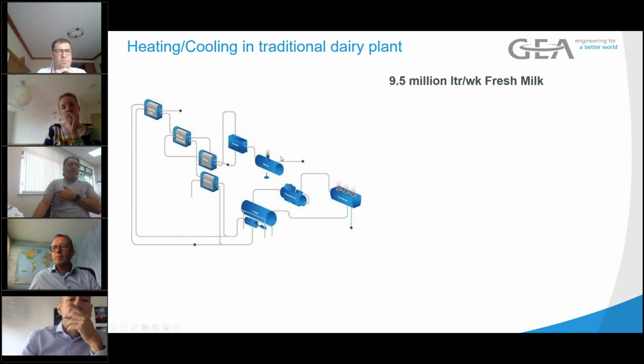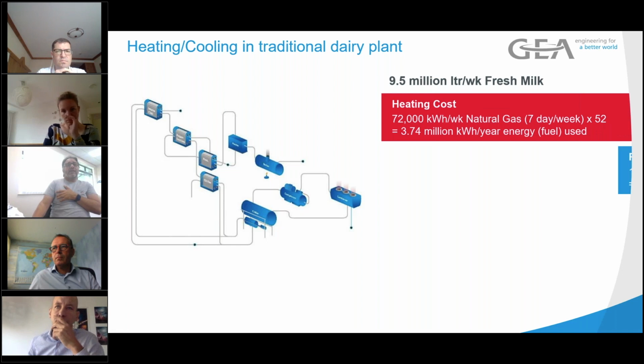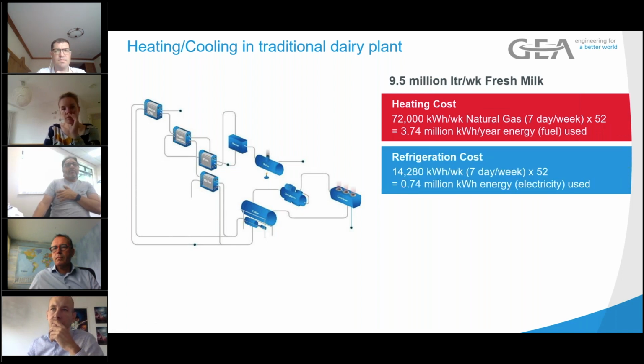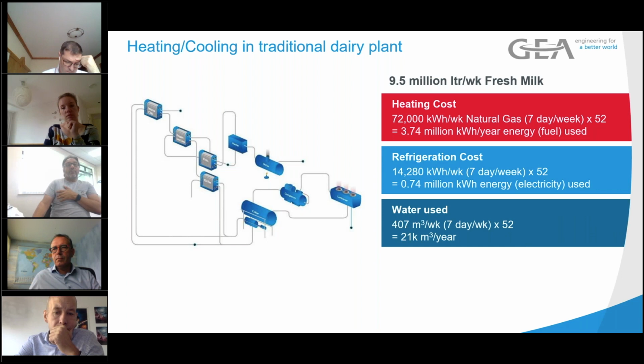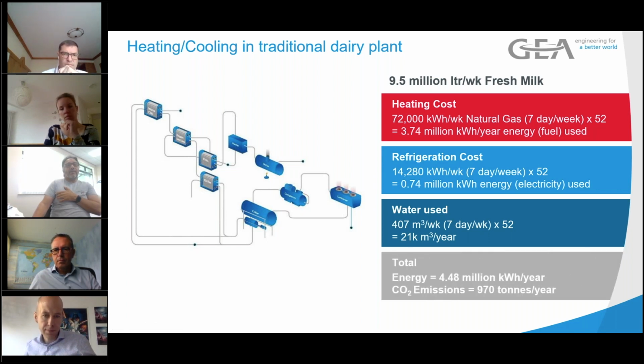And it's the same thing. You got your boiler putting the heat in and the refrigeration plant taking it out. Again, sticking in some figures, it's 3.7 million kilowatt hours of fuel for the heating and 750,000 for refrigeration. And because we were using evaporative condensers in this case, it was 21,000 cubic meters to reject that heat at the evaporative condenser.